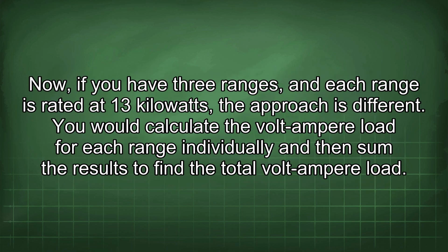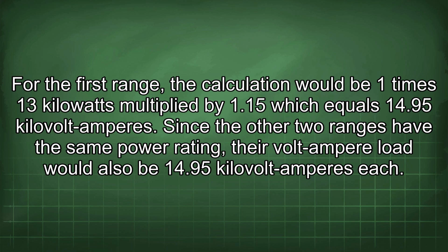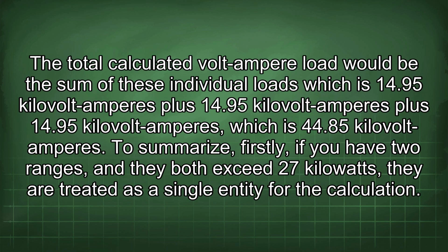Now, if you have three ranges and each range is rated at 13 kilowatts, the approach is different. You would calculate the volt-ampere load for each range individually and then sum the results to find the total volt-ampere load. For the first range, the calculation would be 1 times 13 kilowatts multiplied by 1.15, which equals 14.95 kilovolt amperes. Since the other two ranges have the same power rating, their volt-ampere load would also be 14.95 kilovolt amperes each. The total calculated volt-ampere load would be the sum of these individual loads, which is 14.95 plus 14.95 plus 14.95 kilovolt amperes, which is 44.85 kilovolt amperes.